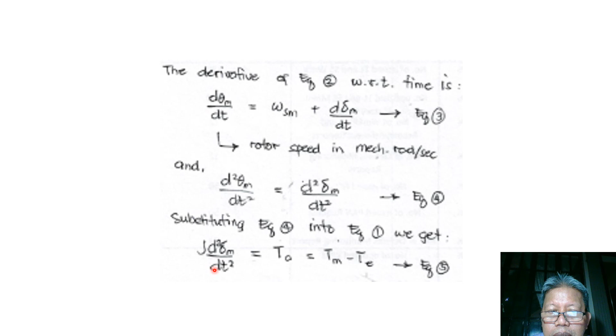Now, in power systems, we usually use power in kilowatts or megawatts. The equation relating torque and power is: power is equal to torque times the angular speed. Let us denote omega m equal to d theta m dt, the angular speed. So multiplying equation 5 by omega m, where omega m refers to the machine, we have J omega m times the second derivative of delta m, dt squared, equal to omega m TM minus omega m TE. Now, omega m TM is the mechanical power, PM, and omega m TE is the electrical power, PE, where PM is the shaft power input to the machine less rotational losses, and PE is the electrical power crossing the air gap of our synchronous generator. So equation 7 may then be written as J omega m times the second derivative of delta m, dt squared, equal to PM minus PE.